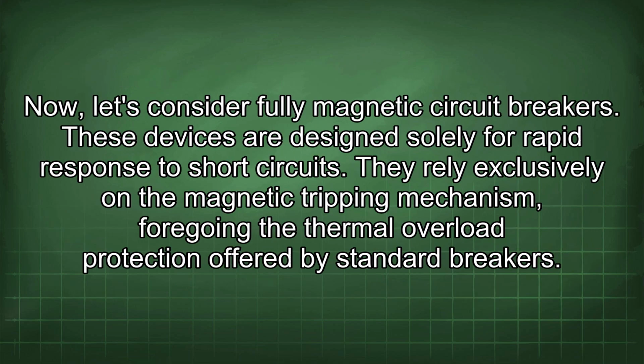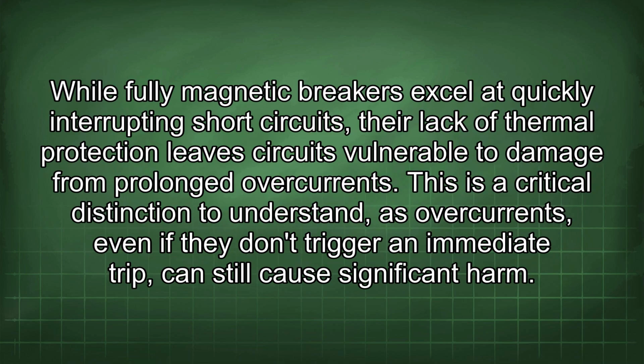Now let's consider fully magnetic circuit breakers. These devices are designed solely for rapid response to short circuits. They rely exclusively on the magnetic tripping mechanism, foregoing the thermal overload protection offered by standard breakers. While fully magnetic breakers excel at quickly interrupting short circuits, their lack of thermal protection leaves circuits vulnerable to damage from prolonged overcurrents. This is a critical distinction to understand, as overcurrents, even if they don't trigger an immediate trip, can still cause significant harm.